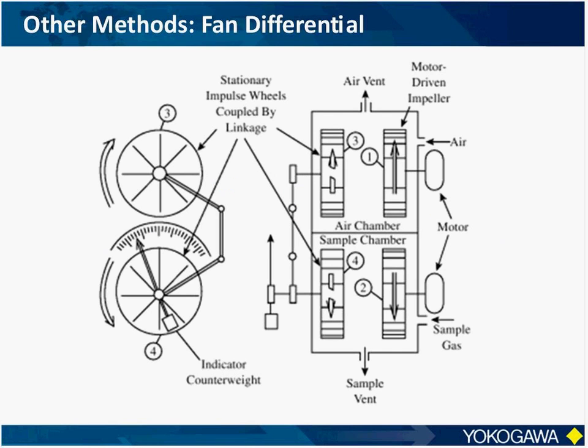One method to measure specific gravity is the fan differential analyzer. It's also known as a kinetic energy or viscous drag type, or by its well-known brand name. This analyzer has two chambers, an air chamber used as a reference and a sample chamber for the measured gas. Each chamber has a motor-driven impeller which draws the appropriate gas into it. Each gas will then come in contact with the stationary impulse wheels and is then vented out of the analyzer.